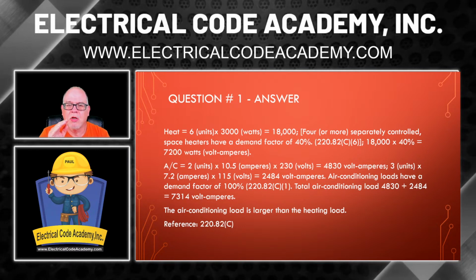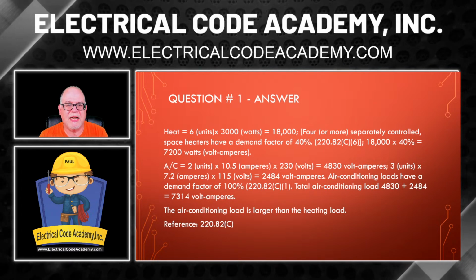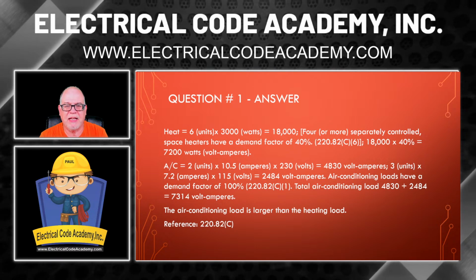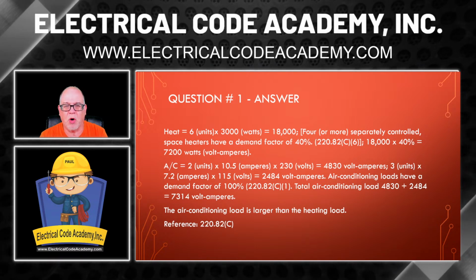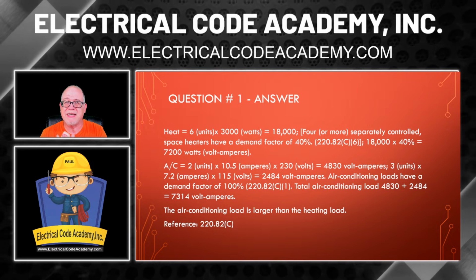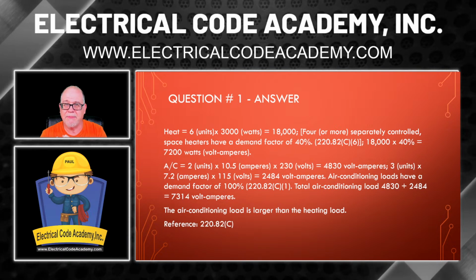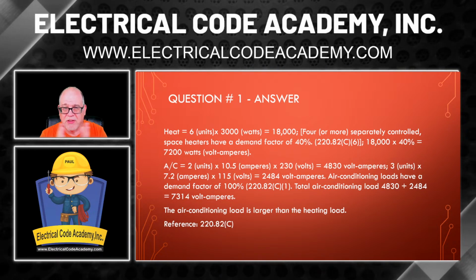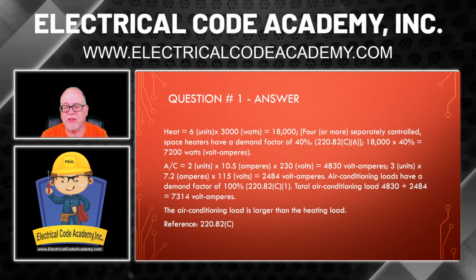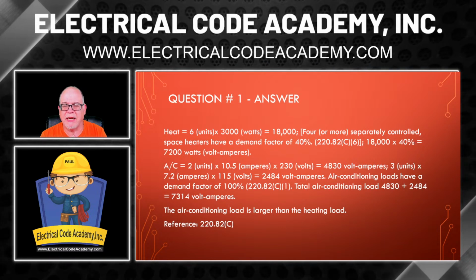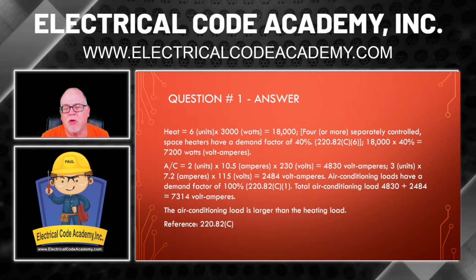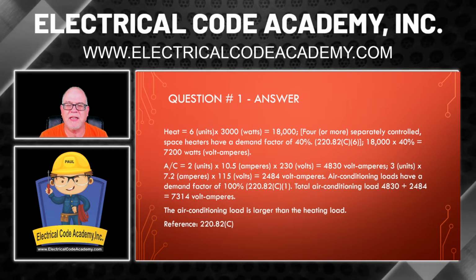All right. So now we want to do 3 times 7.2 times 115. That's 2,484 VA. So all we're going to do is remember, we take them at 100%, right? So we're going to add the 2 together: 4,830 plus the 2,484. That's 7,314 VA.